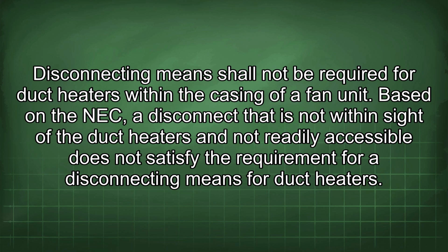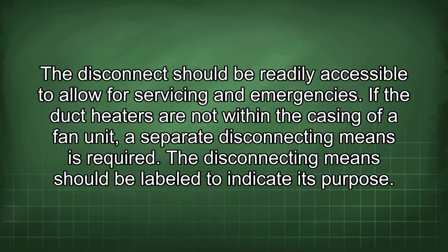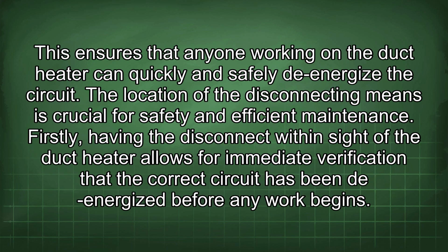Based on the NEC, a disconnect that is not within sight of the duct heaters and not readily accessible does not satisfy the requirement for a disconnecting means for duct heaters. The disconnect should be readily accessible to allow for servicing and emergencies. If the duct heaters are not within the casing of a fan unit, a separate disconnecting means is required. The disconnecting means should be labeled to indicate its purpose. This ensures that anyone working on the duct heater can quickly and safely de-energize the circuit. The location of the disconnecting means is crucial for safety and efficient maintenance.